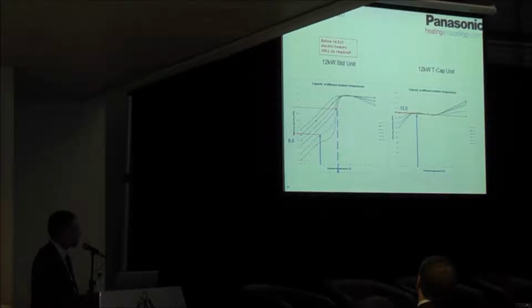So therefore, every time the ambient drops below 4.5 degrees C, we're utilising electric heaters, which is going to have a significant effect on the end user's bills. Whereas a 12 kilowatt TCAP unit will give you 12 kilowatts all the way. It's only when it gets to about -8 that you do have a small bit of drop off.